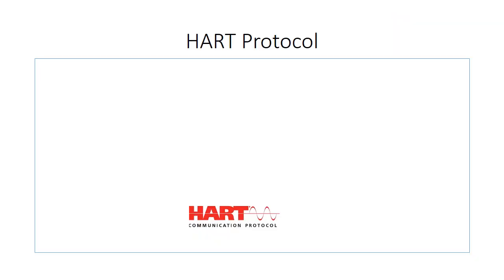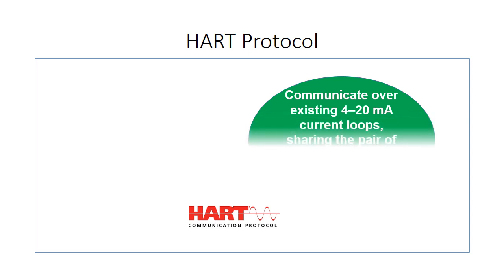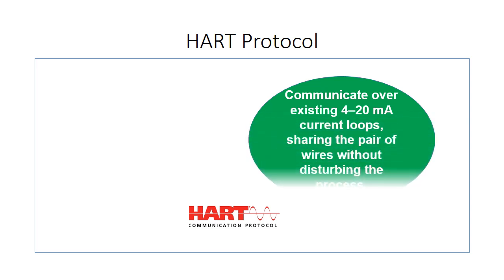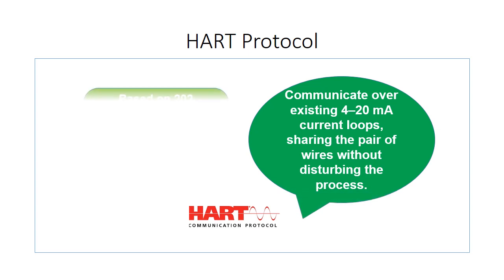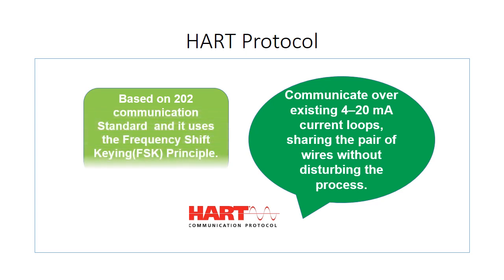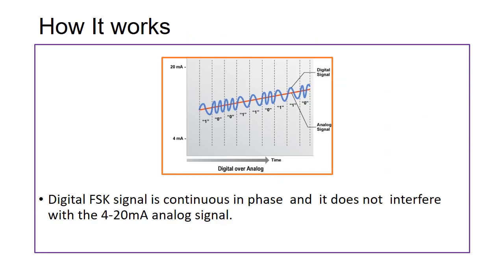The most important advantage of HART is that it can communicate over existing 4 to 20 milliampere analog current loop, sharing the pair of wires without disturbing the process. HART is based on the Bell 202 communication standard and it uses the frequency shift keying (FSK) principle.